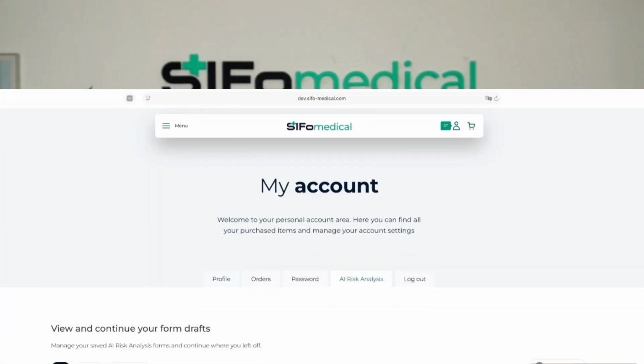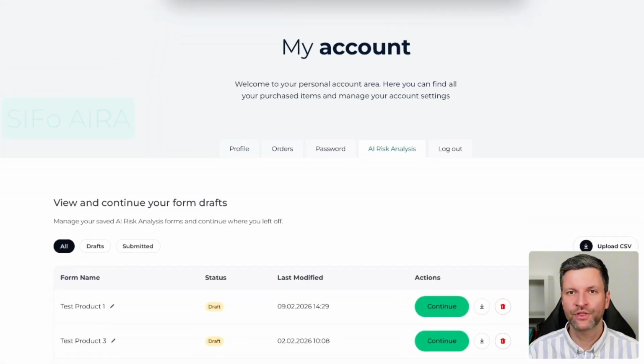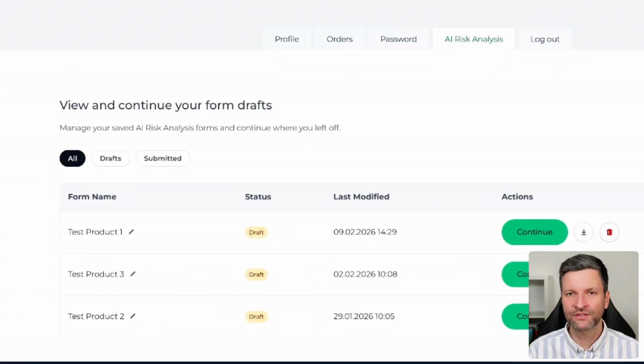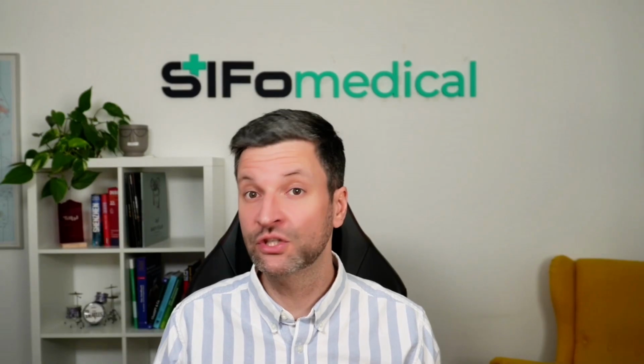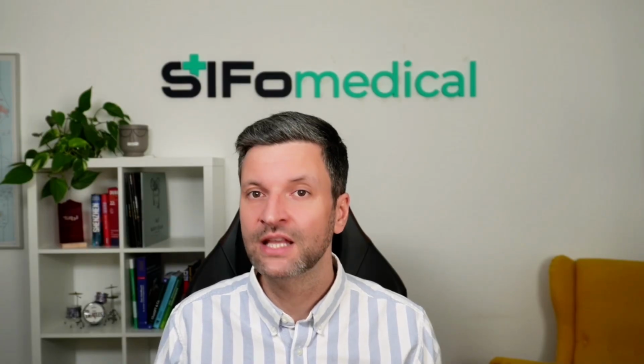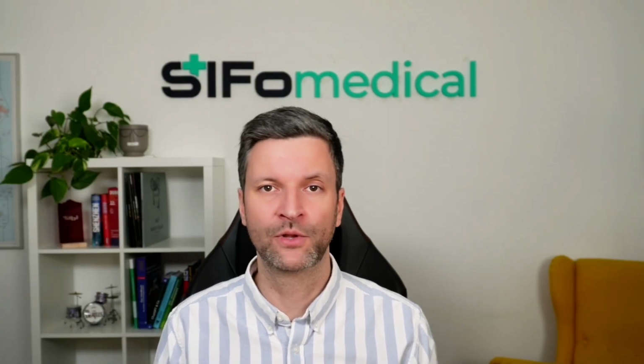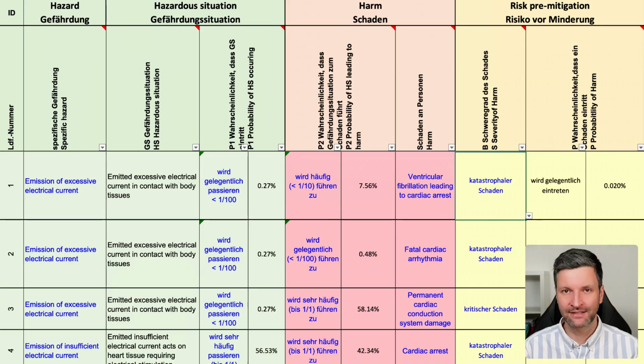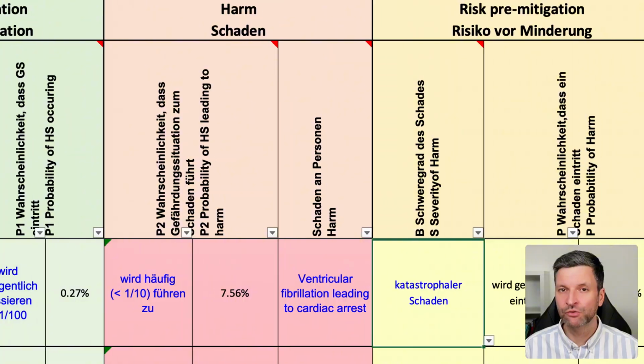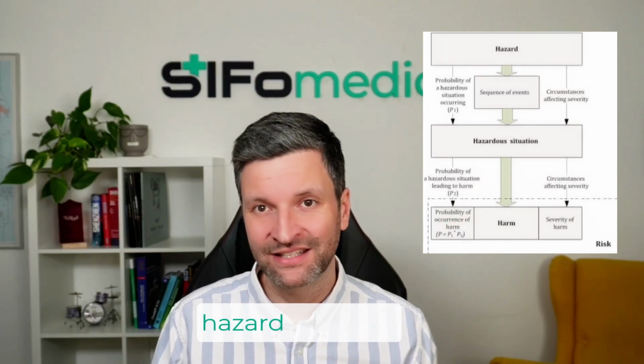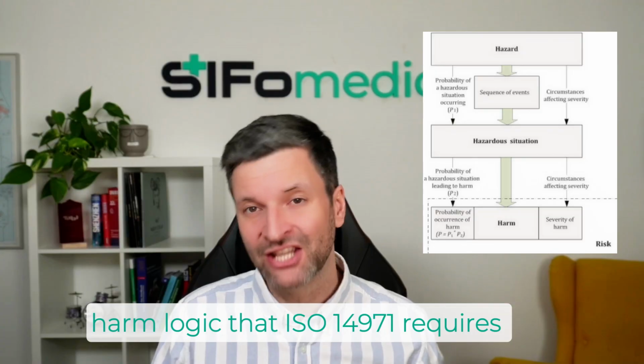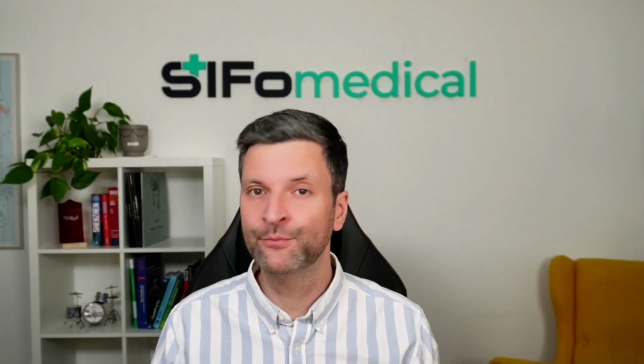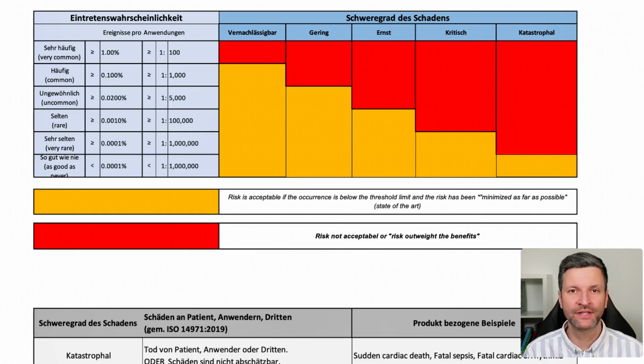What you are seeing is the main interface. Instead of starting with a blank template, you begin by answering a structured questionnaire. You describe your device, its intended use, the clinical context, and the user population. The AI then generates a comprehensive risk analysis: hazards, hazardous situations, potential harms, and initial risk ratings. It follows the hazard, situation, harm logic that ISO 14971 requires and provides P1, P2, and severity assessments based on industry data and best practices.